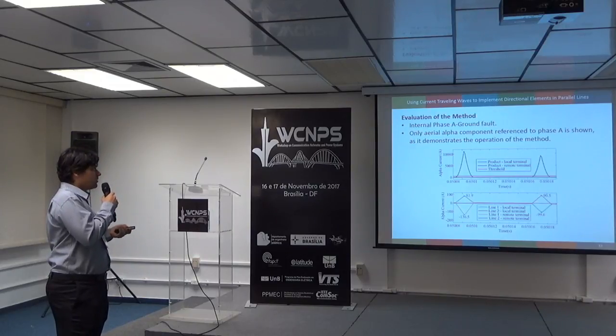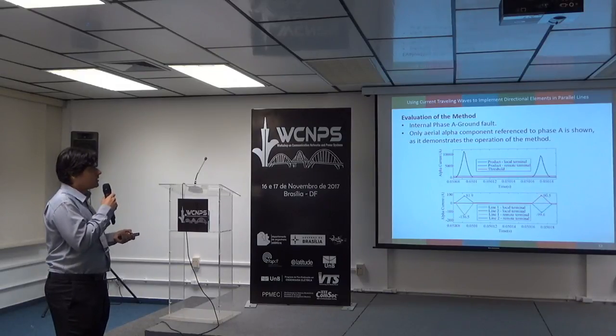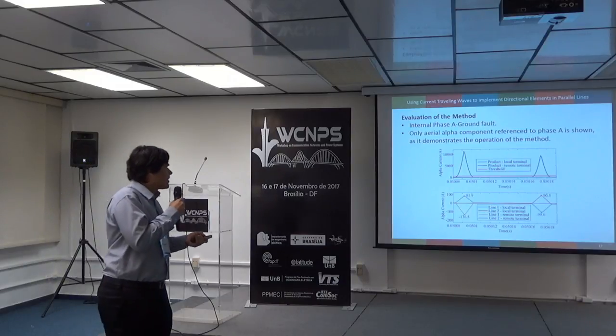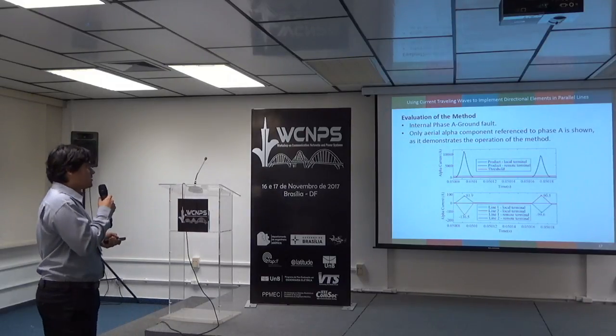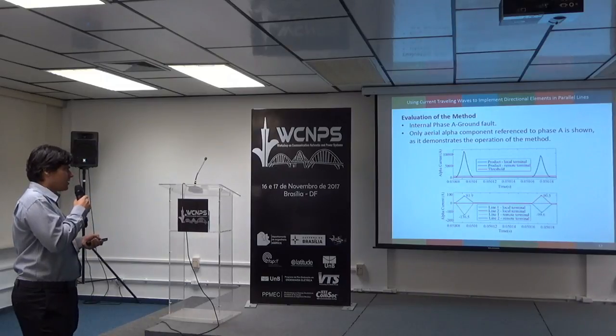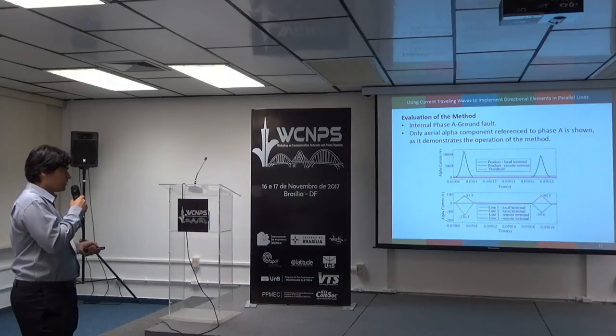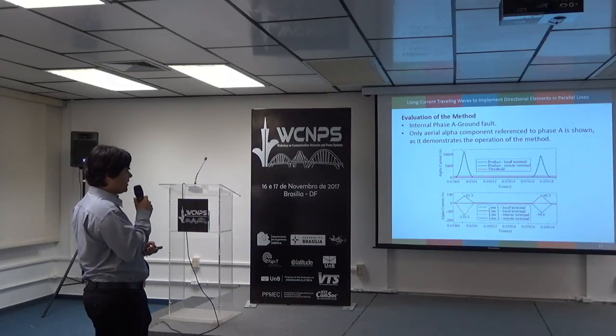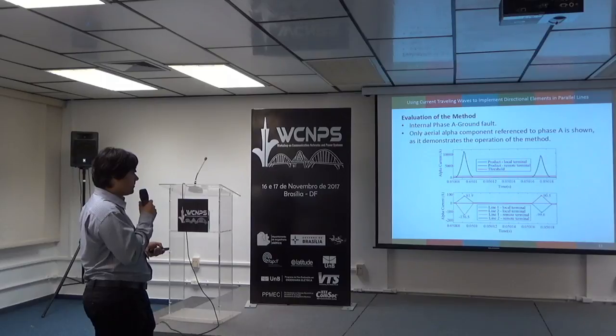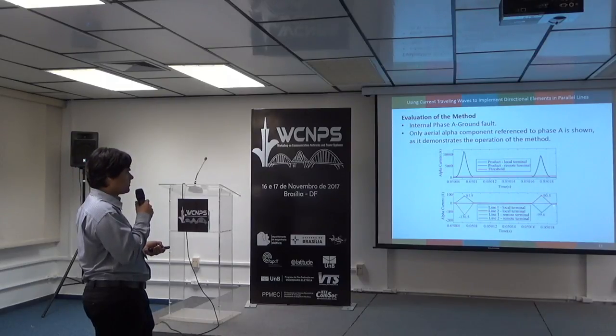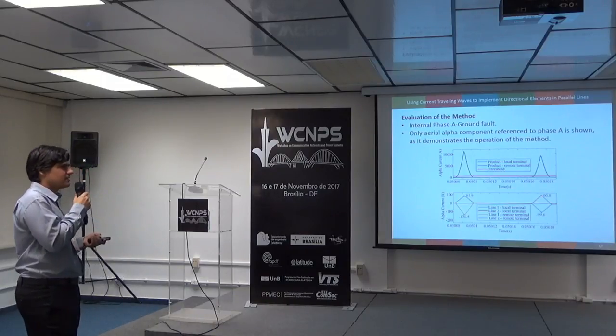In the case of internal, we show here only the aerial alpha component, reference to phase A, as it demonstrates the operation of the method. As you can see, the threshold is exceeded for both terminals, and as you can see here, line 1 is the fault line, and the greater values indicate the fault line. That is line 1, as we expected.